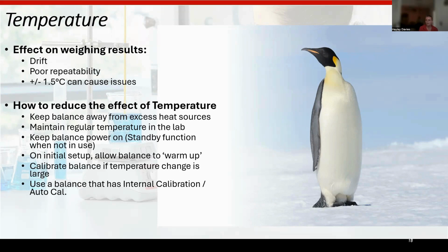Heat sources can include a fridge blowing out hot air at the back, or direct sunlight. Try to maintain a regular temperature in the lab, away from heaters and direct sunlight. If the balance has just been turned on, give it time to warm up. This is more relevant for laboratory balances; if it's a semi-micro balance, we recommend leaving it on, turning it on overnight, and giving it time to warm up.